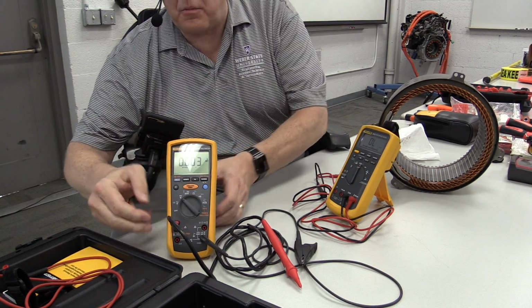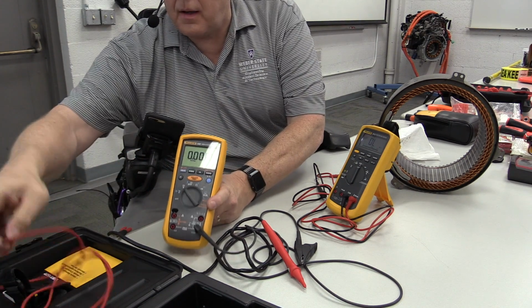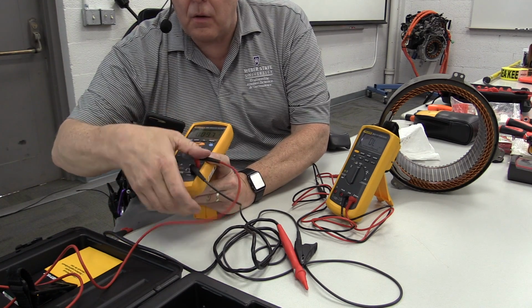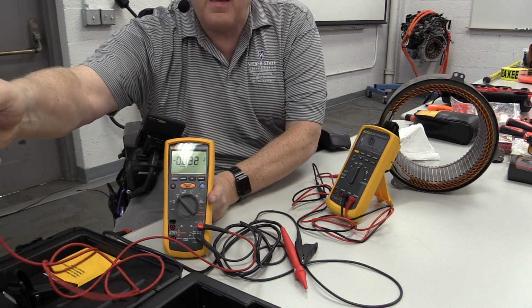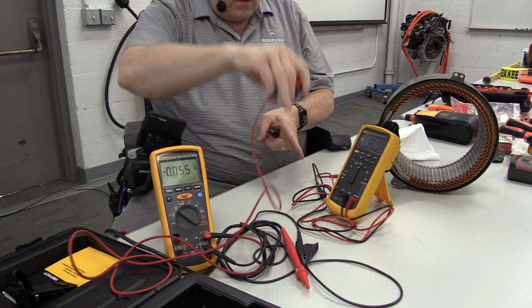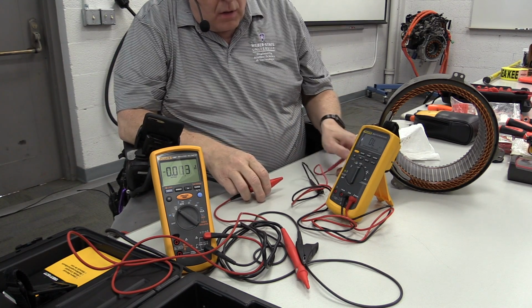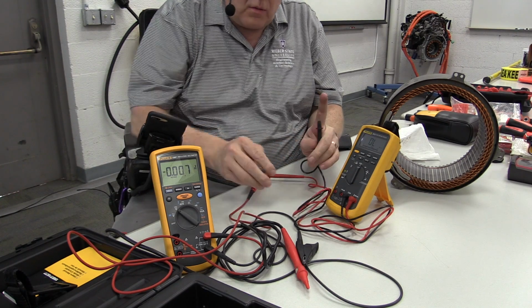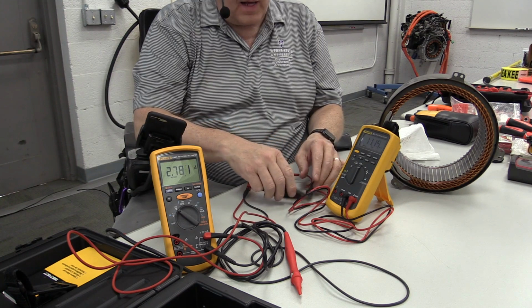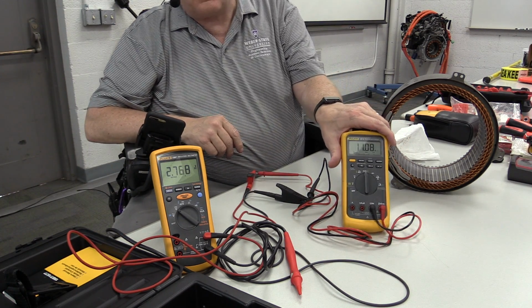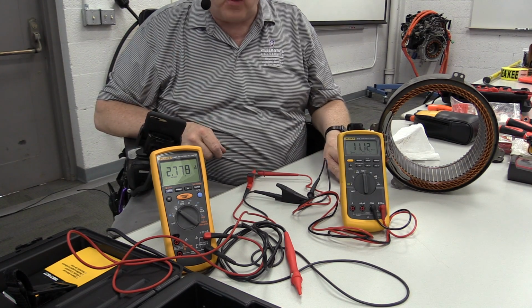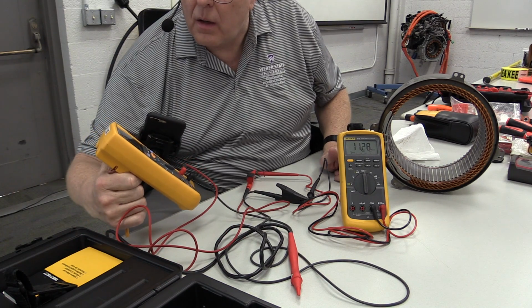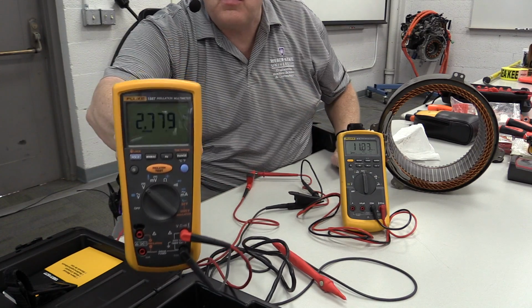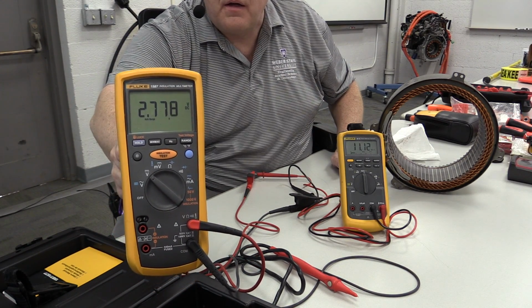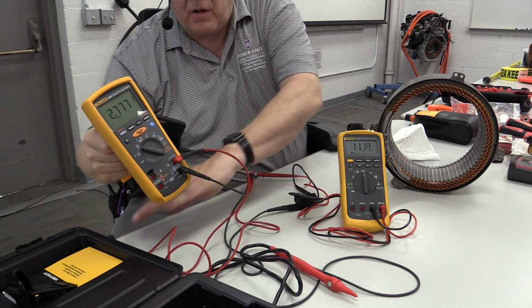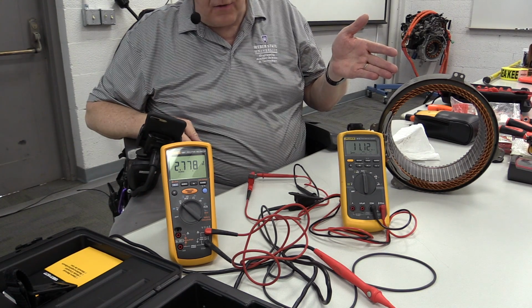So if we take the Fluke 1587 meter and take out our resistance checking probe and put in the multimeter probe instead over here, what we are going to measure is the voltage that the Fluke 87 uses to measure resistance. So we'll just hook red to red, black to black. The Fluke 87 is on ohms. The Fluke 1587 is on volts. So that's telling us that the Fluke 87 is using 2.7 volts to measure resistance on that stator winding. 2.7.